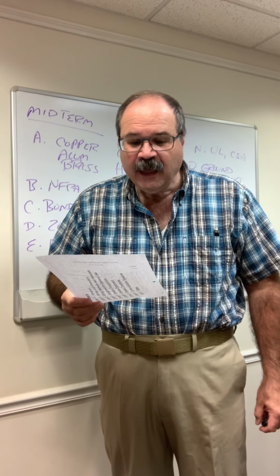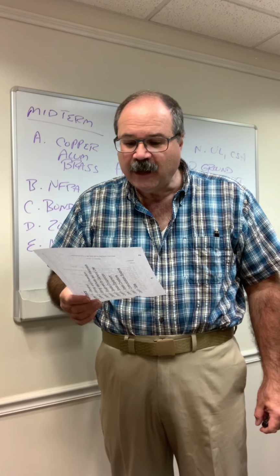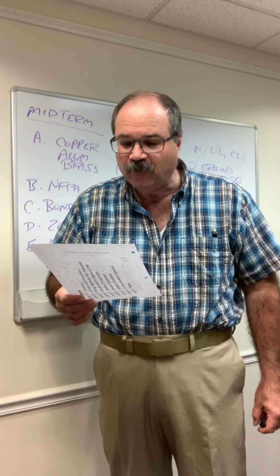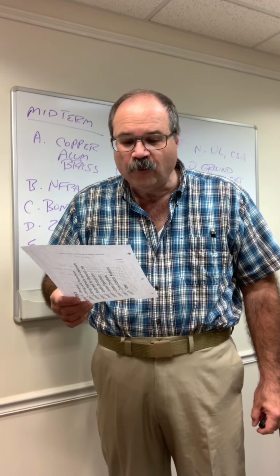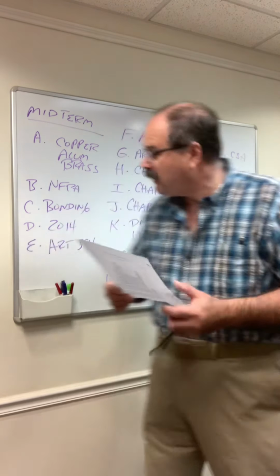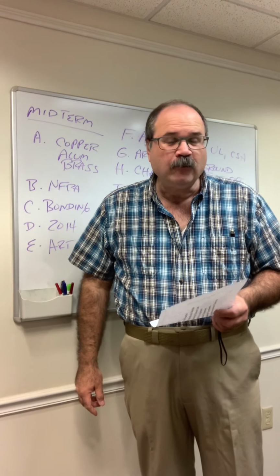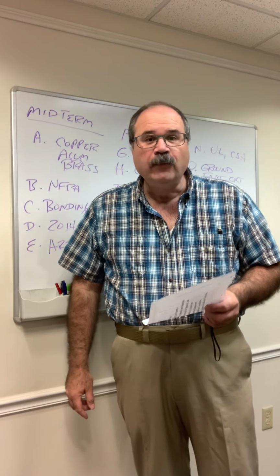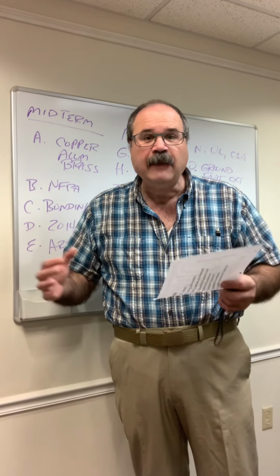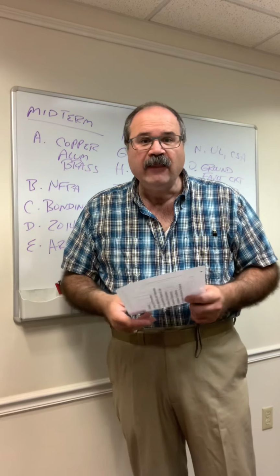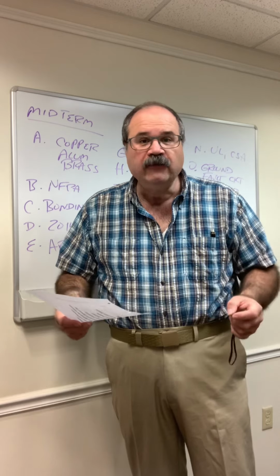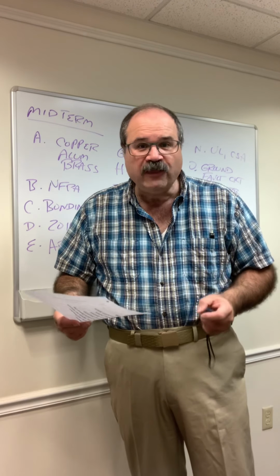Question C, a number 12 bare copper wire is attached to a pull box. Would this be a grounding or a bonding function? This would be a bonding function, and we will talk about this in depth when we get into Article 250, but for now, think of whenever we tie metal to metal together, that's a bonding function. Whenever you tie something to the earth, that would be a grounding function.